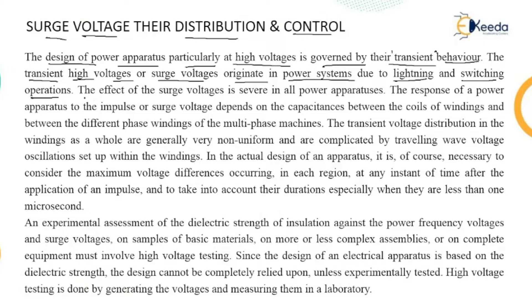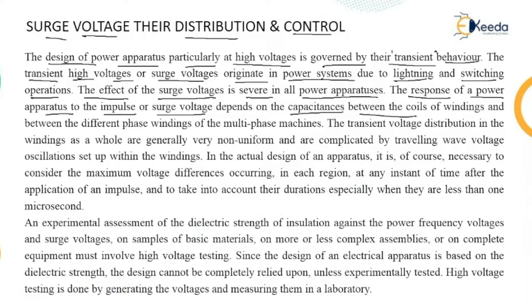The effect of surge voltage is severe on all power apparatus — it affects all apparatus connected between the generating plant and the load center. The response of a power apparatus to this impulse or surge voltage completely depends on the capacitances between the coils of windings and between different phase windings of multi-phase machines.